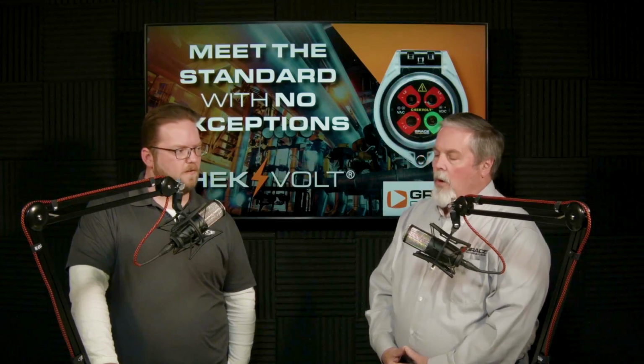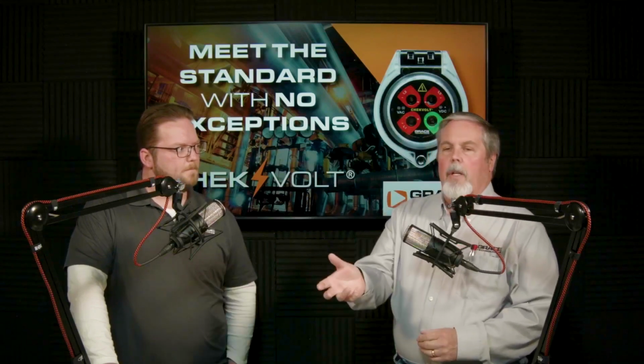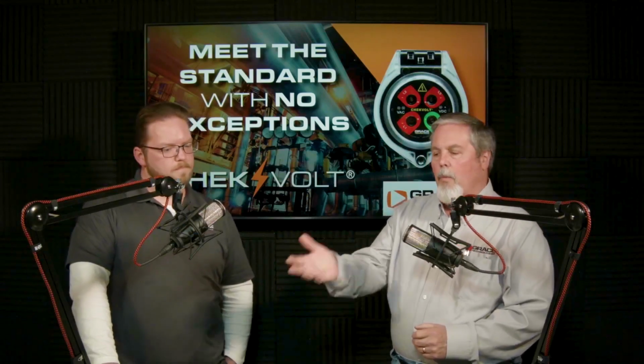Correct. Okay. So what we've done, as you just mentioned, is we've brought the energy to the outside of the cabinet. We actually have a high impedance circuit, so we reduce the available current when you're taking your measurement. The electricians and the safety team and a lot of the maintenance people trust their meter. They want to use their meter. They're going to come up to the unit. They're going to see that it is flashing.